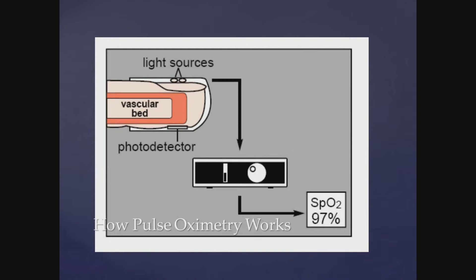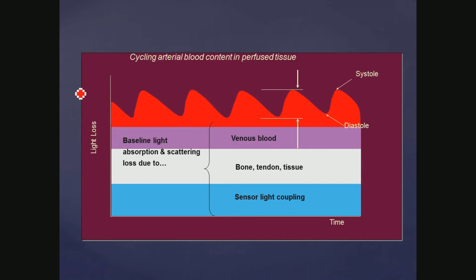We know that there's a lot of artifact, and we're using two components. The photospectrometric method is used to discern which wavelength of light we're looking at. So the one specific for SpO2 is different from the one for reduced hemoglobin. And we're using the plethysmography component to identify at what point we want to do this measurement. Obviously we want to do it at peak systole when the pulsatile flow is the greatest, because that's going to give us the biggest change in oxygenation. All the other stuff that is there is basically artifact that you end up having.